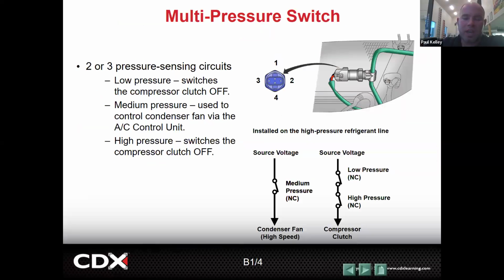They also have pressure switches, and sometimes they're wired up together. For example, the low pressure switch is normally closed, and the high pressure switch is normally closed. If your low pressure gets too low, it'll open, which cuts power to the compressor. If your high pressure switch gets too high, for protection it'll open, cutting power to the compressor clutch. See how we can use a lot of them in series? We just put them in series, boom, boom, boom. It's an interesting way of doing it.